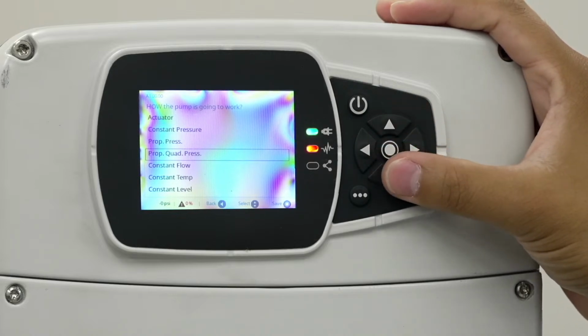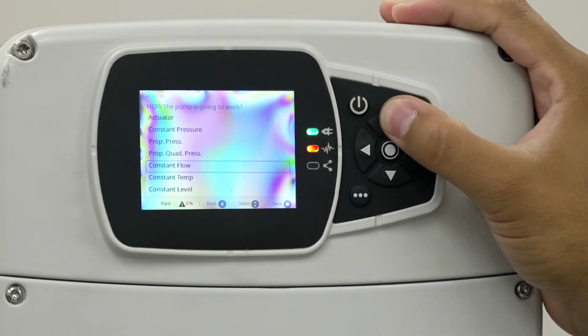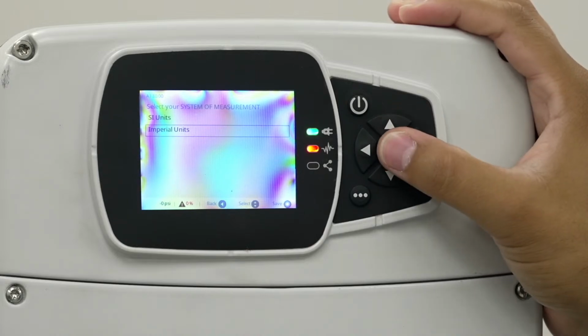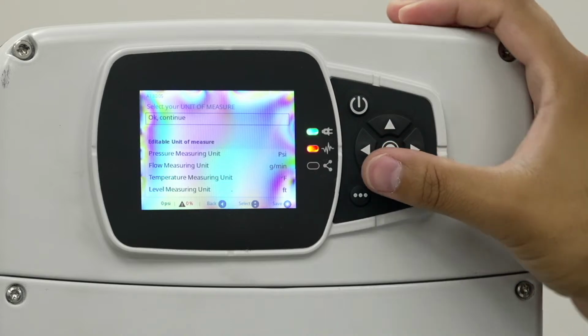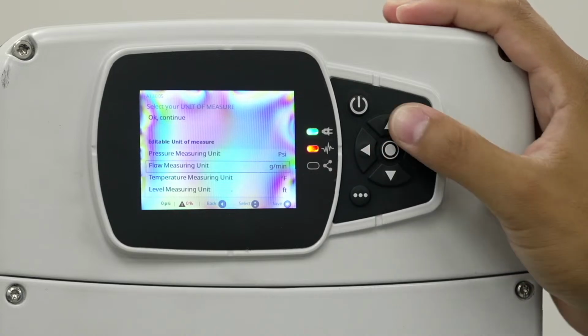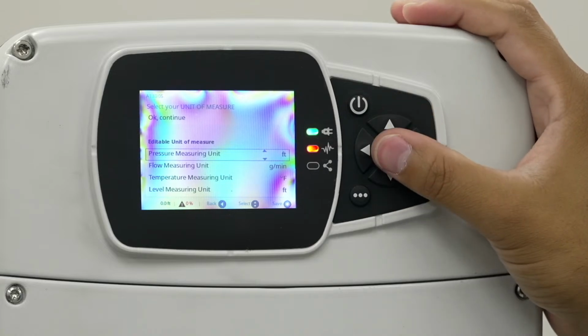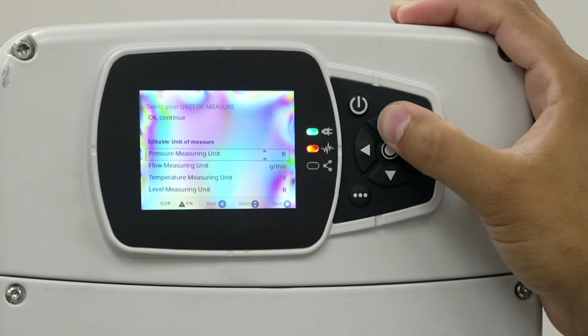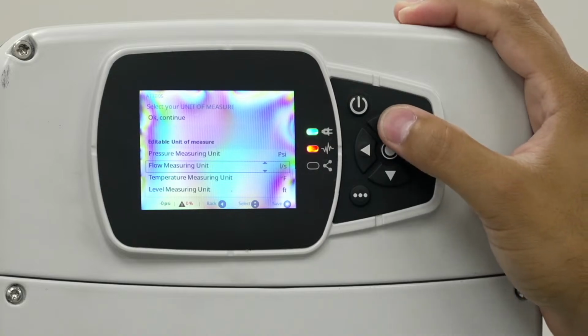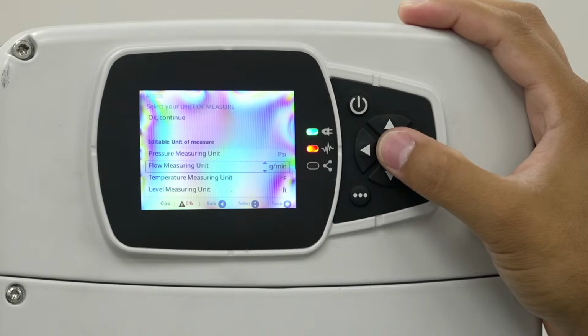And then a bunch of different modes. We touched on them before, but constant pressure, proportional pressure. You can see your constant flow, temperature, level. We'll go with constant pressure. And then units, SI units or imperial. So I clicked imperial. Now it's saying, do those units look good? If you don't like something and you still want to tweak them, maybe they all look good, but instead of seeing pressure in PSI, you can click on it and say, no, I'd rather have this in feet of head. You can go ahead and cycle through. There's a lot of different options. We'll keep it on PSI, but similarly, you can go through any of these and adjust or fine tune them if you didn't want that specific unit of measure. But if it looks good, you go back up to OK, continue.